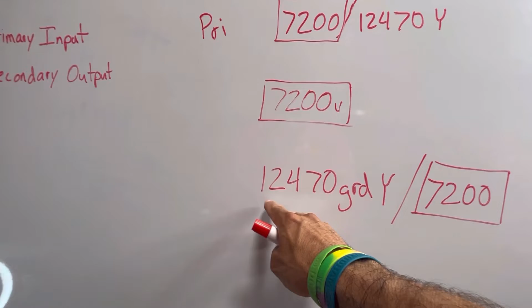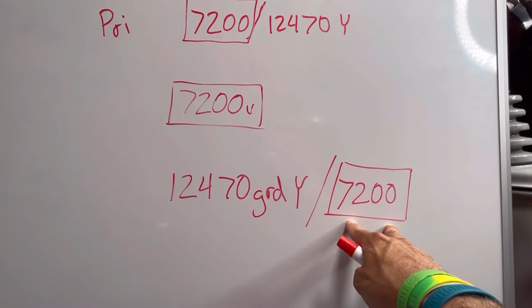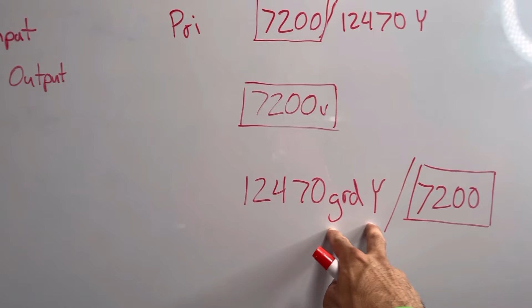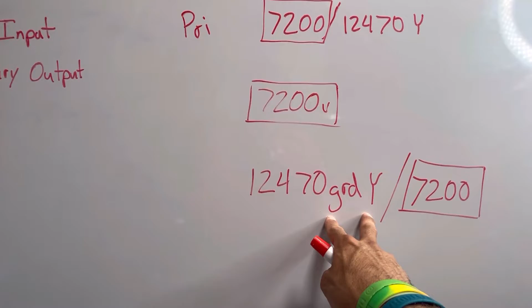And this transformer specifically, when it tells you the information like this, 12470 grounded Y / 7200, it's telling us something else. It's telling us that we need 7200 volts running through that primary coil. And the second thing that it's telling us is this transformer specifically has to go on a grounded Y circuit. And the reason for that, it does not have two insulated primary bushings. What this one actually has, it will have one insulated primary bushing.